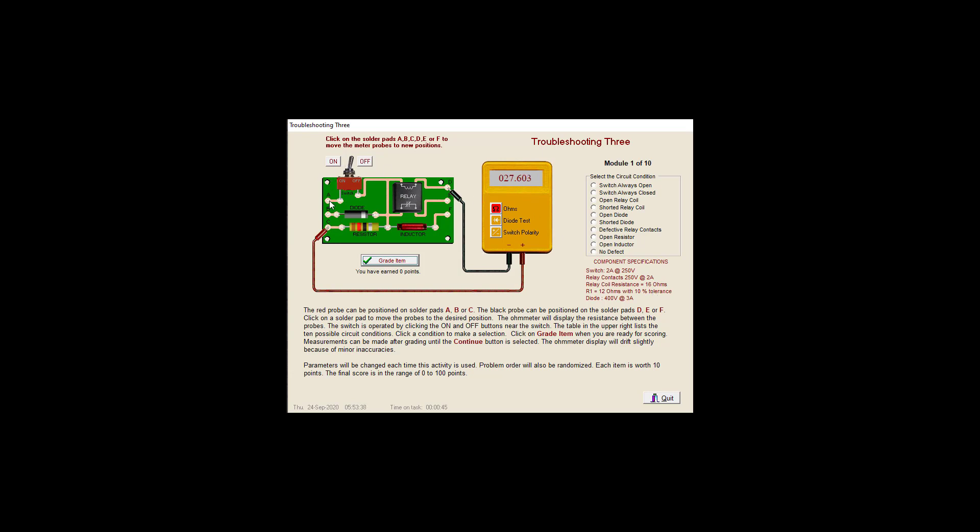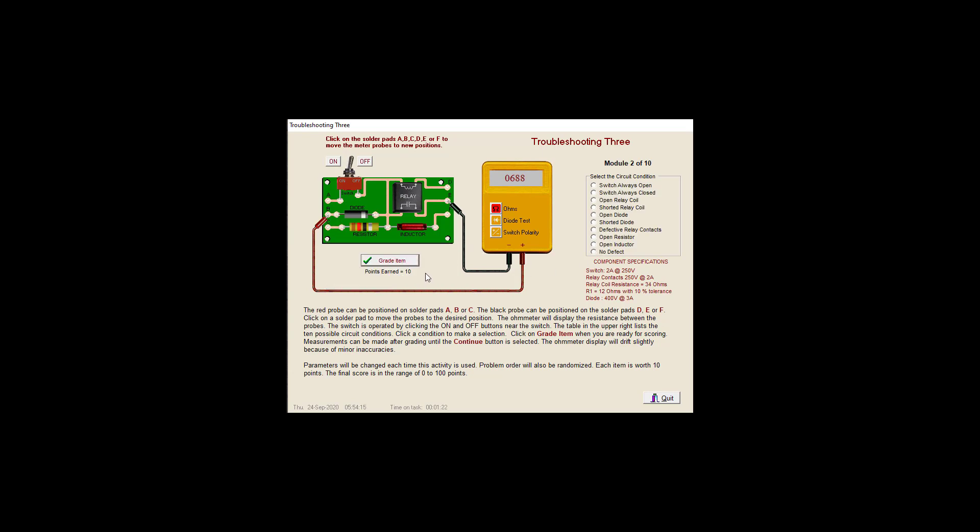Let's check our switch. 15. That's a little on the low side, but that's okay. So let's go check our diode. Let's go through our contact here. Okay, so we have infinite ohms. That means we've got an open. So let's check our diode. And our diode's good. Okay, so he looks okay to me.